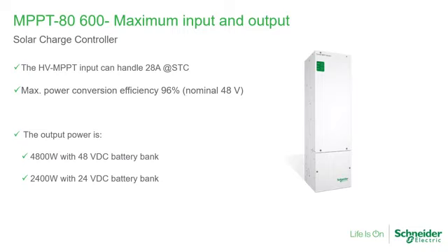Now, one thing is that say you have oversized the array, but you have optimum irradiation. The array is in the perfect angle. And the only reason why the array was oversized is because we were trying to accommodate the losses that the modules will suffer across the life expectancy. What's going to happen in the very beginning is that you're not going to output more than 80 amps. So you will see some clipping on the peak sun hours, around noon, right? So again, oversizing is okay to accommodate the life expectancy of the system. However, the output is 80 amps. So that will not change.